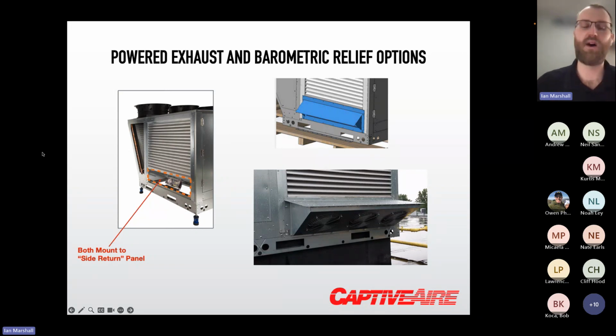We also have a powered exhaust module, which utilizes our energy recovery wheel module, which I'll get into a little bit, but without the actual energy recovery wheel. So it's a whole other module mounted on the unit with a direct drive plenum fan. Or we can utilize this barometric relief here as well.